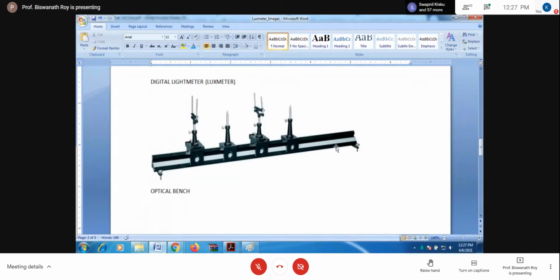In the first hand, we place the lux meter, what we call the test lux meter, that is to be calibrated, and the power supply to the lamp is given from what we call a controlled voltage, constant voltage, constant frequency power supply, so that we can vary the supply voltage very accurately, right, with the first place of decimal, right.